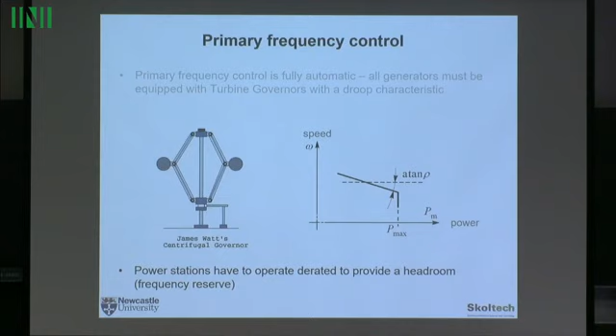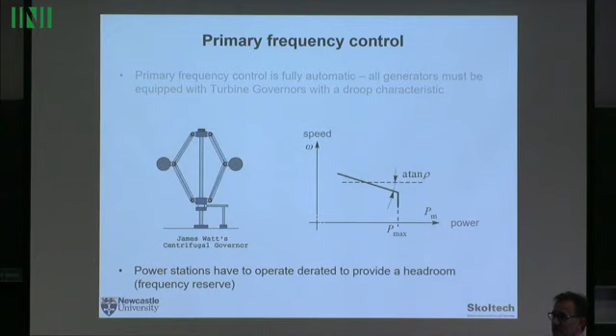In Australia, because they've gone crazy about liberalization, frequency control is a market service that people can opt out of. Power stations hate it because it means their turbines have to go up and down constantly, and they prefer to work steady. So the system operator has to pay people for it, and they may opt out if they wish. As a result, they had a blackout because frequency control didn't work properly. In most other countries it's an obligatory service; you don't get connected unless you provide it.